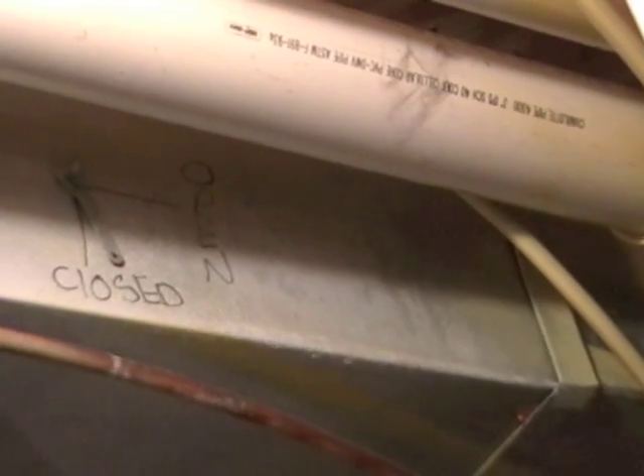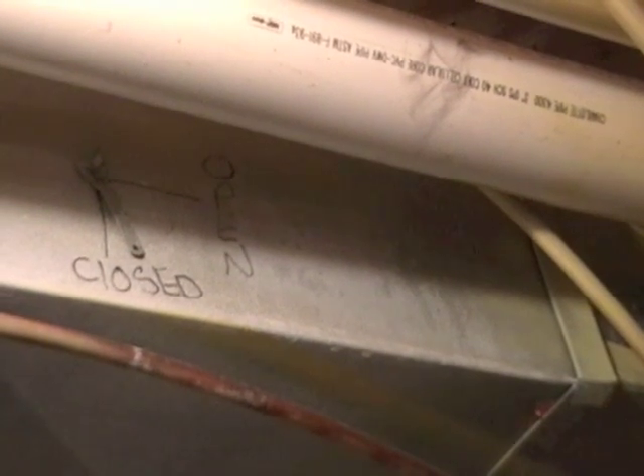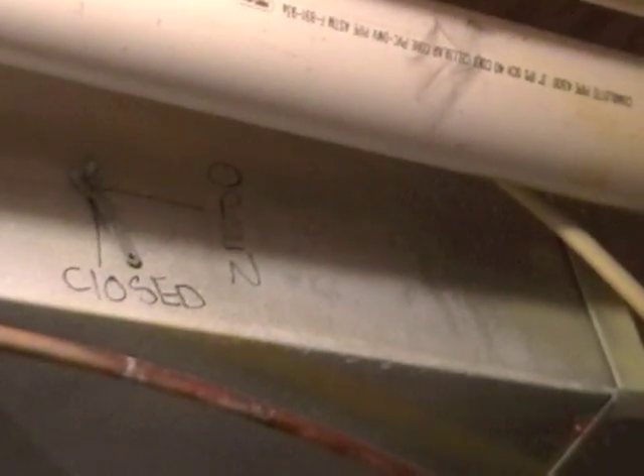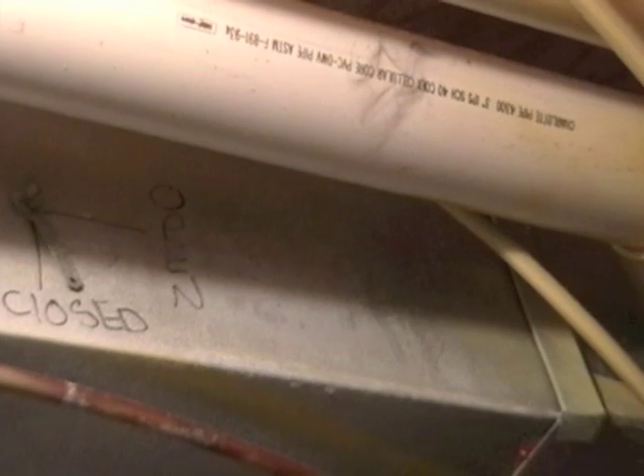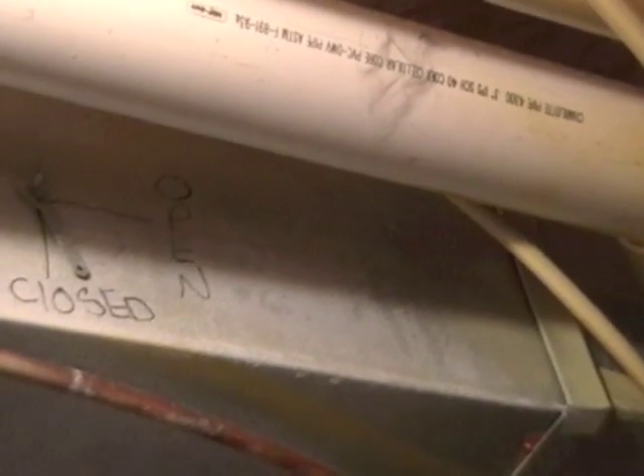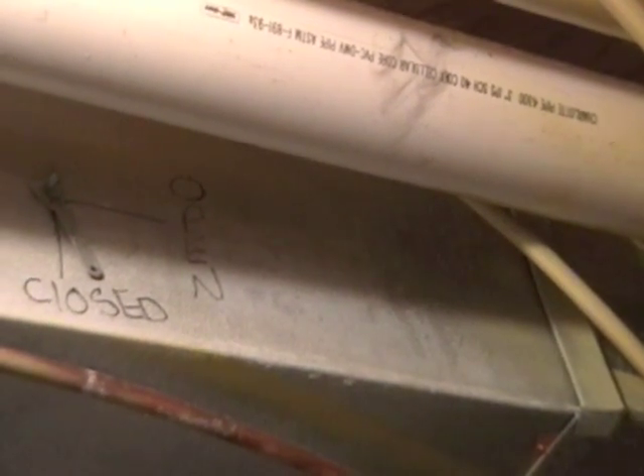This is where you could use a buddy to work with on the top floor with a cell phone. Give the air a minute to travel. Have your partner feel the force coming out. When you feel the level of flow is good, you also now regulate the registers in each room, depending upon which ones you prefer air to come from and which ones you do not. You should most commonly open the registers on the upper level all the way, close the registers halfway on the main level, or as comfort dictates, and the lower level registers should be 90% closed. Your goal might be to have no more than 5 to 8 degrees variance in all 3 levels.